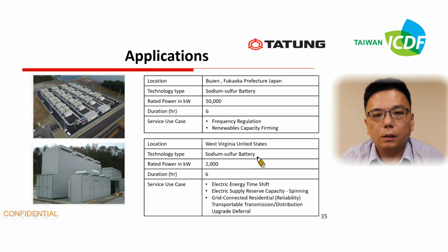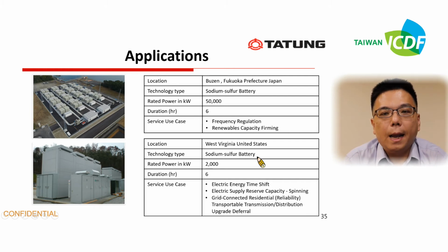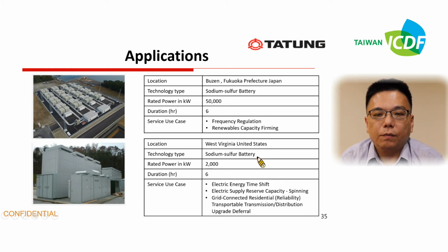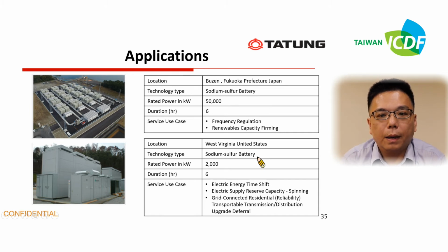Its service use cases are frequency regulation and renewable capacity firming, and you can see the rated power is 50 megawatt, and the duration is higher than 6 hours. It is a very long duration compared with other battery systems. The second sodium-sulfur battery system is located in West Virginia, United States.